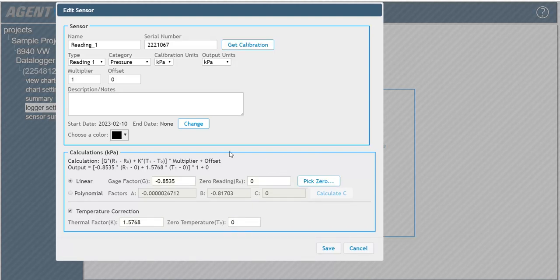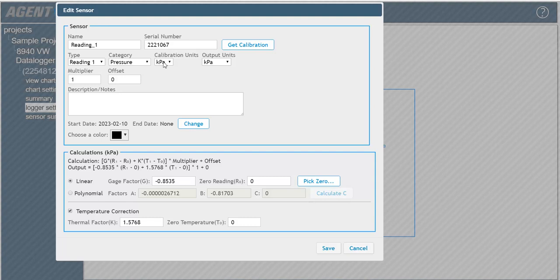For multi-channel loggers, the type field is used to select the channel the sensor is wired into. For addressable loggers, the type field is used to select the position of the sensor in the string. The category indicates what type of measurement the sensor is taking. The calibration units must match the engineering unit of the gauge factor taken from the calibration report.